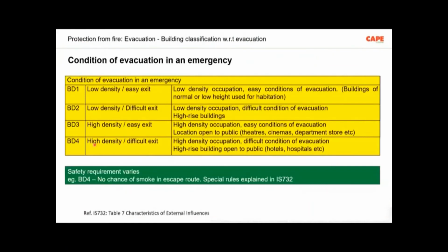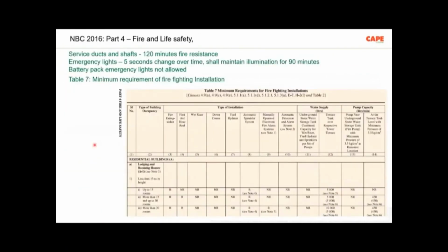Now, when it comes to the National Building Code, Part 4, Table 7 explains the classification and minimum requirements of firefighting installations. In the upcoming National Electrical Code, probably 2022, which will come in maybe 3-4 months, we tried to combine the requirements of NBC and IS 732 in a different way. If we look at the NBC, service ducts and shafts should be fire resistant for 120 minutes. The electrical installation for emergency services should have 120 minutes fire resistance, whereas if we look at IS 732, the minimum requirement is 1 hour. But anyway, we have to follow the National Building Code. Emergency lights should switch over within 5 seconds. Battery pack emergency lights are not allowed. These are actually influencing the safety.